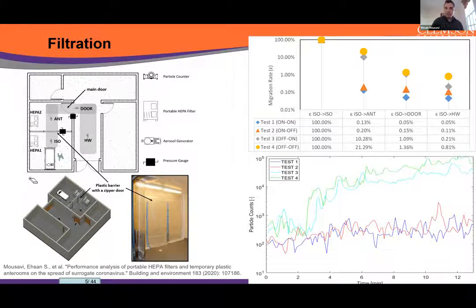So we turned both of them on. We turned only the isolation room HEPA filter 1 on, and you can see the different variations that we tested. The interesting result is that it matters. Actually, it matters very significantly which HEPA filter you turn on and what that system looks like. If you look at this, when both of the systems are off, I have a trend in particles, and this is right at the door, outside of the room.